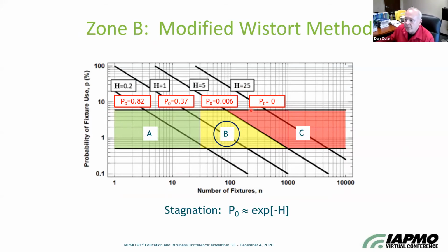But as the building type becomes smaller, we see that the probability of no flow becomes increasingly larger. So when you're down to a single family home, the probability that there's not going to be any water flowing at all is significantly high. And this is what Hunter did not take into account with his curve, which we have taken into account with the water demand calculator.